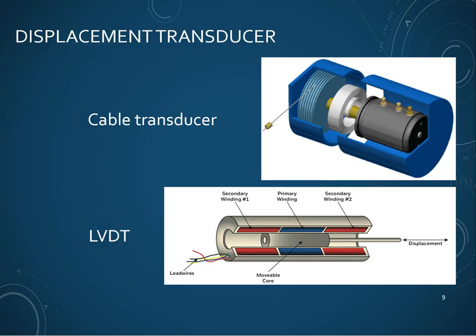Displacement transducers are another class of vibration measurement devices. These include cable transducers and linear variable differential transducers (LVDTs). The physics involve magnetic coils where displacement results in changes in the magnetic field of these coils, which result in changes in voltage that we can measure via data acquisition systems. We can then relate the measured voltage changes to changes in displacement.